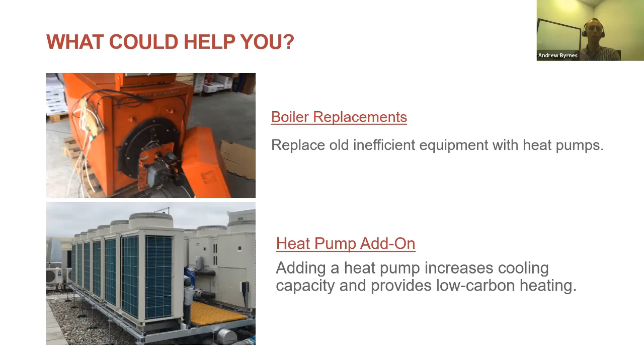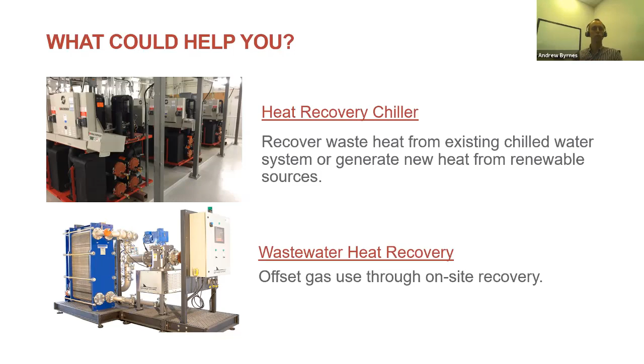Heat recovery chiller is also a great option, especially in buildings where there's a large simultaneous heating and cooling load - strip malls, large MURBs, places with a mix of office and residential, or a high domestic hot water load. These are all great candidates for a water-to-water heat recovery chiller that produces usable heating water and usable cooling water at the same time. Wastewater heat recovery can also be either on-site or off-site from wastewater flows.